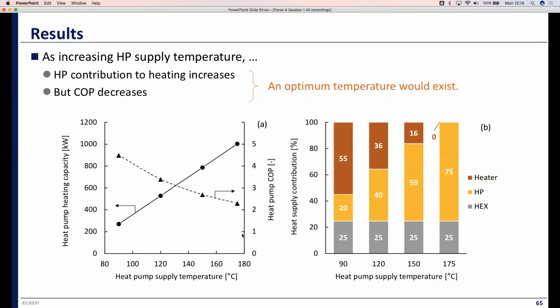As shown in the right graph, the heat supply contribution by the heat exchanger accounts for 25%, regardless of heat pump supply temperature. When the heat pump supply temperature is 90 degrees C, the heat pump contribution is only 20%. But when the temperature is 175 degrees C, of course, all of the heat supply can be covered with the heat pump and heat exchanger.